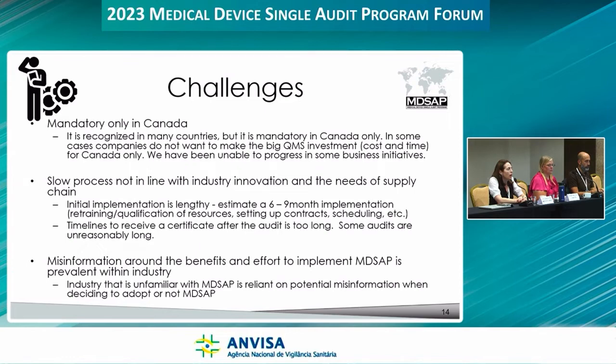6 to 9 months. And the one thing that I found very interesting when I was in industry and as I moved into this association is this ongoing misinformation around the benefits of MDSAP and the cost of MDSAP. I found myself speaking to someone, I think from the UK, and I asked some key questions: do you have ISO 13485? Yes. Do you already get audited by the FDA? Yes. So I told them, you are already more than halfway there to MDSAP. The difference is not as much as you think and the cost is not as much as you think. And he's like, oh, hold on, I wasn't aware of that.